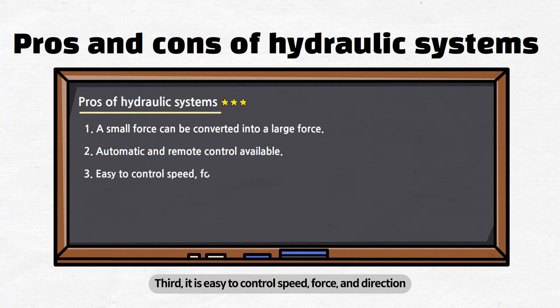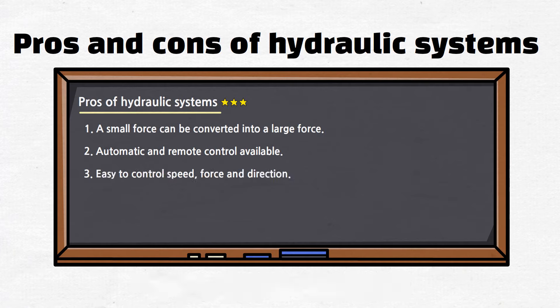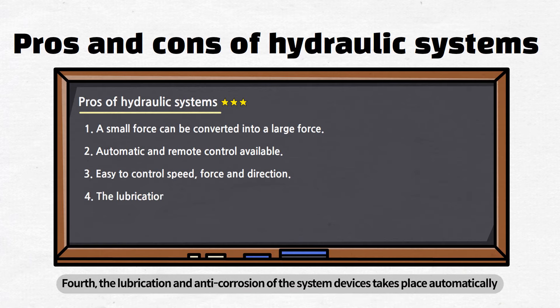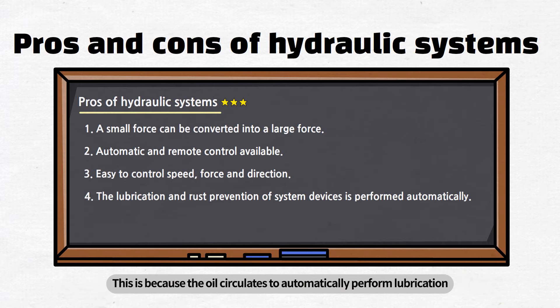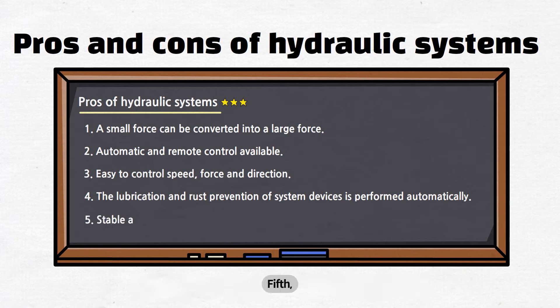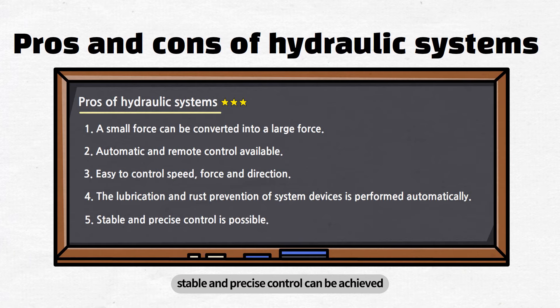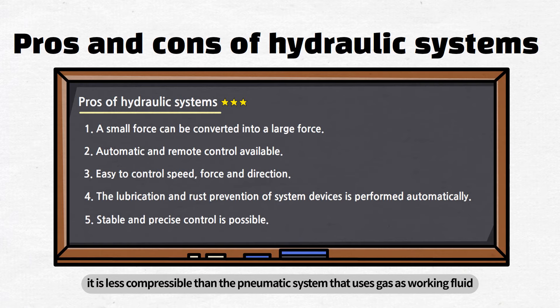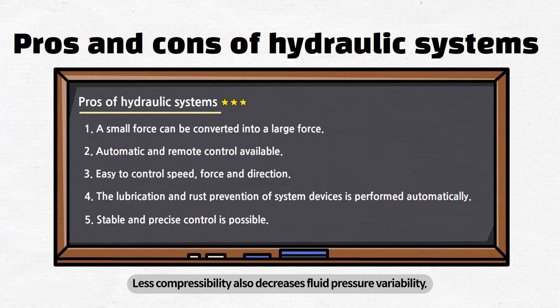Third, it is easy to control speed, force, and direction. Fourth, the lubrication and anti-corrosion of the system devices takes place automatically, because the oil circulates to automatically perform lubrication and anti-corrosive actions on the system devices, thereby effectively reducing wear and corrosion problems. Fifth, stable and precise control can be achieved. As liquid is used as working fluid, it is less compressible than the pneumatic system that uses gas as working fluid. Less compressibility also decreases fluid pressure variability, ensuring more precise control.